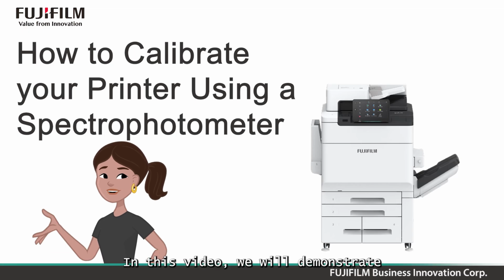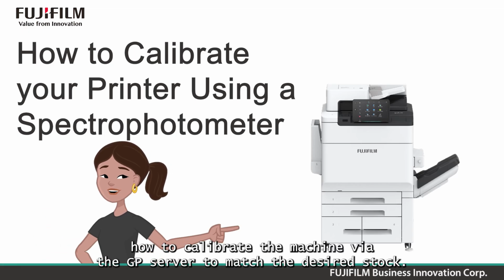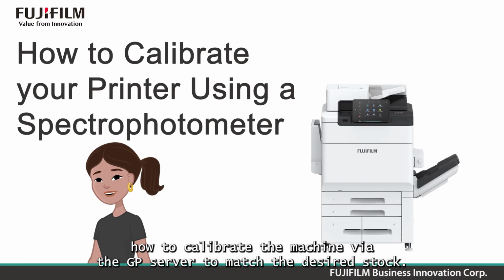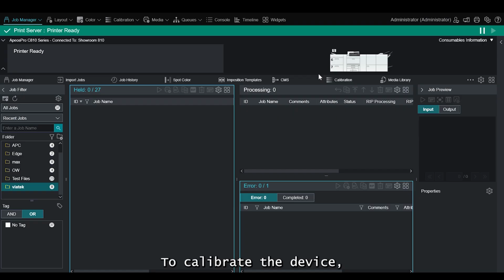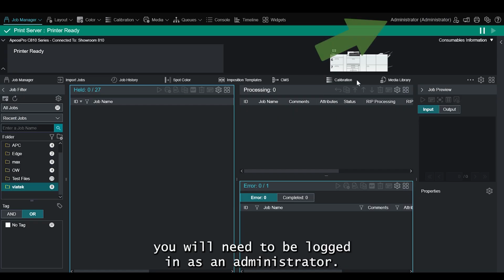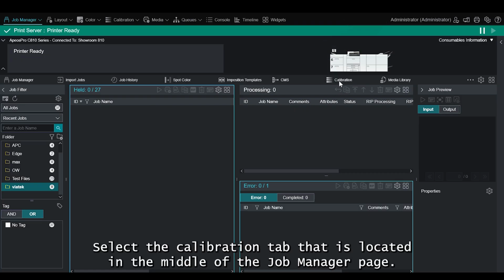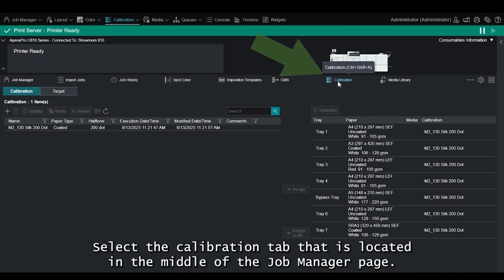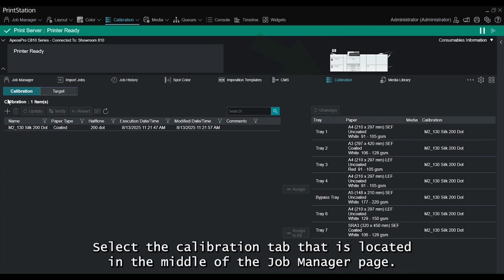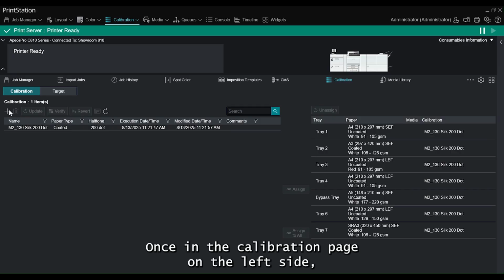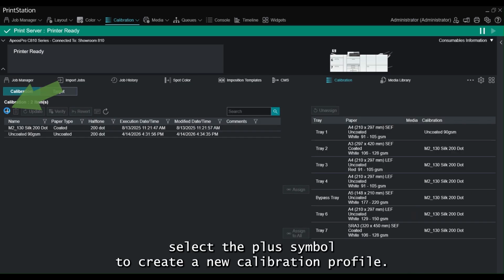In this video, we will demonstrate how to calibrate the machine via the GP server to match the desired stock using a spectrophotometer. To calibrate the device, you will need to be logged in as an administrator. Select the Calibration tab that is located in the middle of the Job Manager page. Once in the Calibration page, on the left side, select the plus symbol to create a new calibration profile.